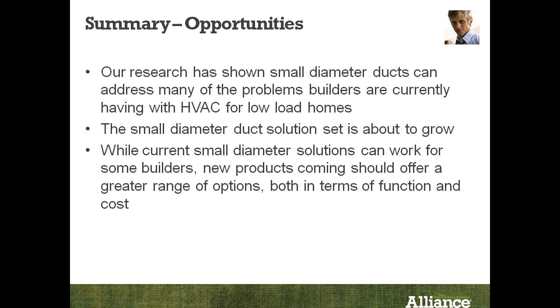And as we look at these new products, we consider them in light of the existing products. What's undesirable about traditional pressure regain duct systems is that they're highly engineered, and they require being installed very well. What we see is the engineering side isn't done accurately every time, because when an HVAC design engineer does the work, he doesn't consider where the trusses are, where the rafters run. So they may make mistakes, and then when it's actually installed in the field, it may not look like the design that the engineer designed. And even if it is exactly as the engineer designed, the craftsmanship may not be to the level that they anticipated. So we know that there are problems on those two fronts. So when we talk to people about the ideal plastic duct system, we consider it in light of these two deficiencies with existing ducts.